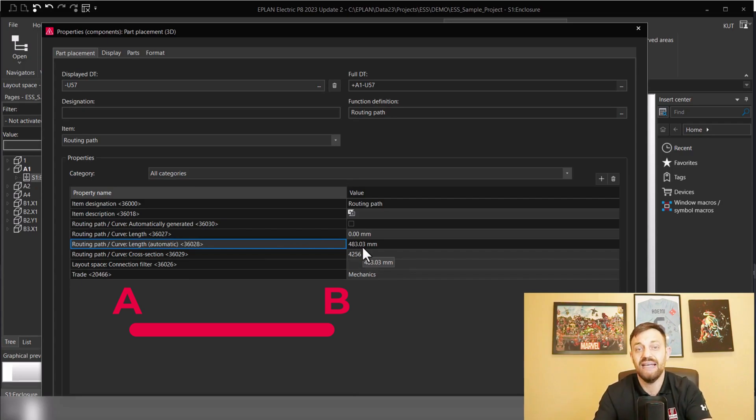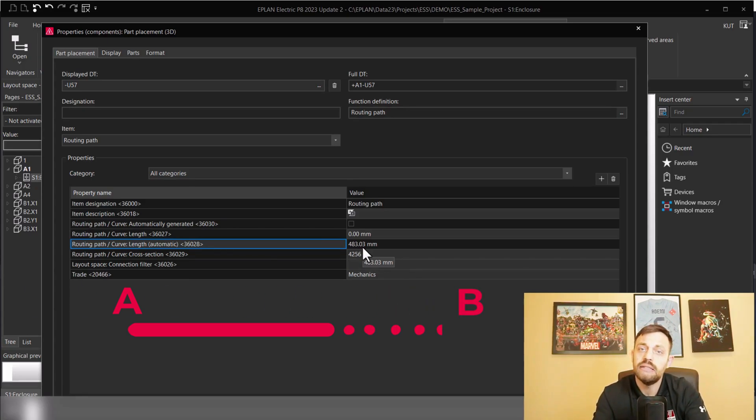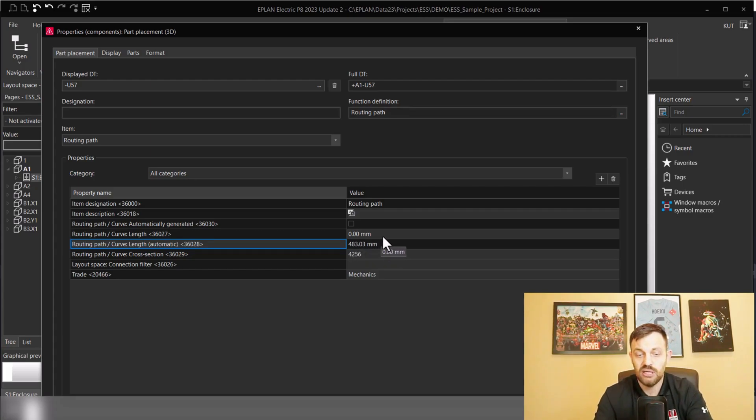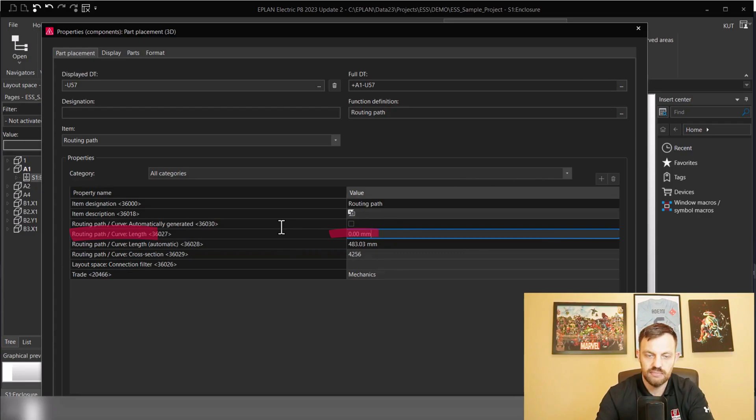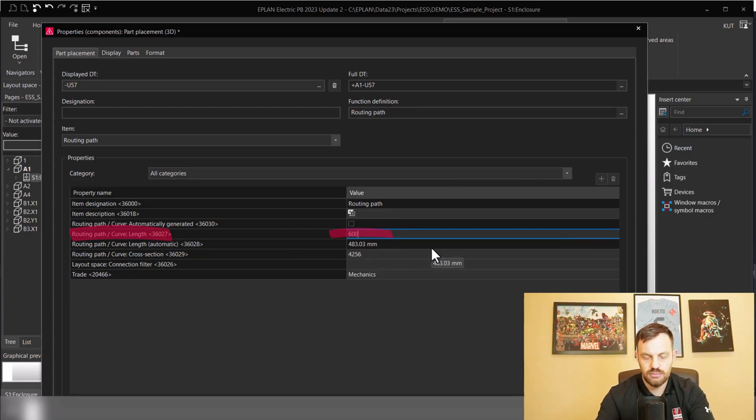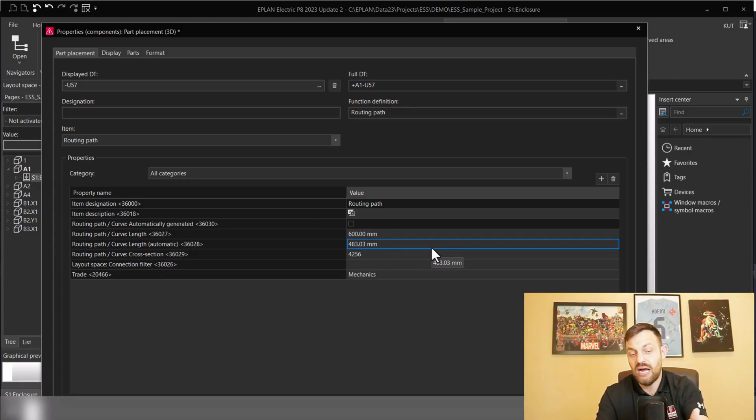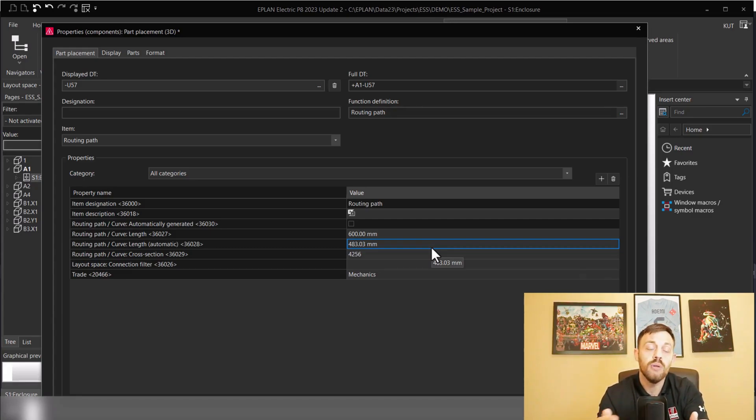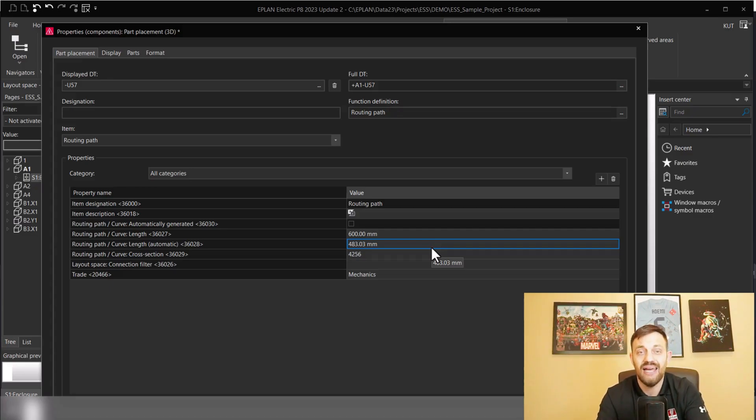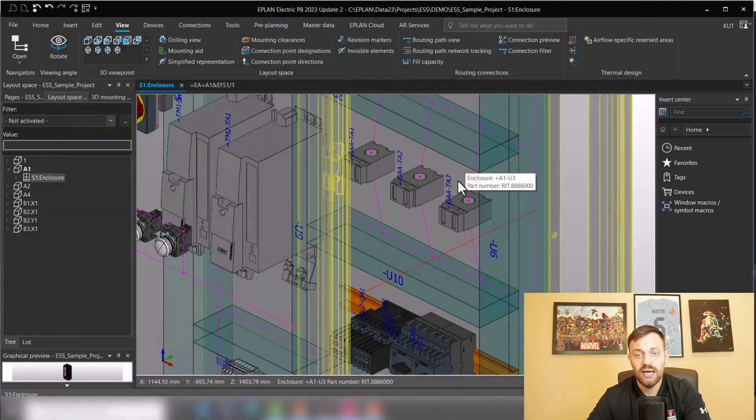If I now want to add additional length, for instance to calculate in the bending of the door, you could instead of 483 millimeters say here 600 millimeters. And now every wire which goes through the segment will be around 130 millimeters longer, and you will have enough room to wire the connection between the door and the mounting panel.